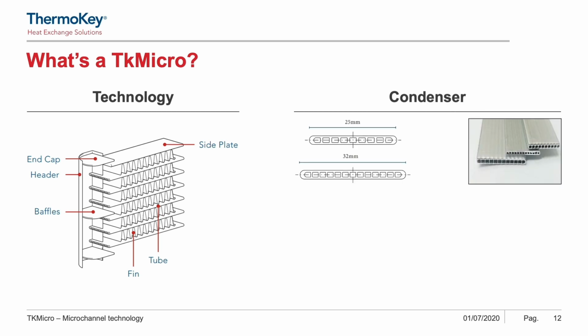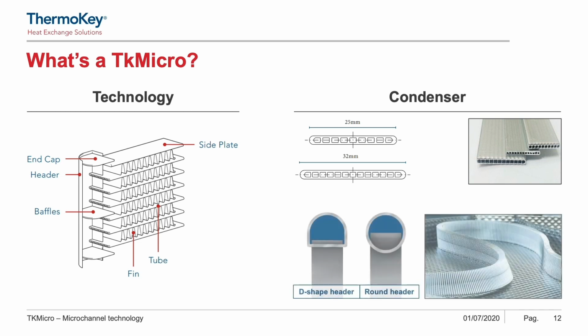Microchannel use dedicated tube profiles accordingly to the application. In the case of condenser, it is key to guarantee a fully developed phase change of the refrigerant and to minimize the pressure drop across the microchannel cores. The combination of tubes and manifolds is designed for this aim, and it has been developed through long R&D activities.